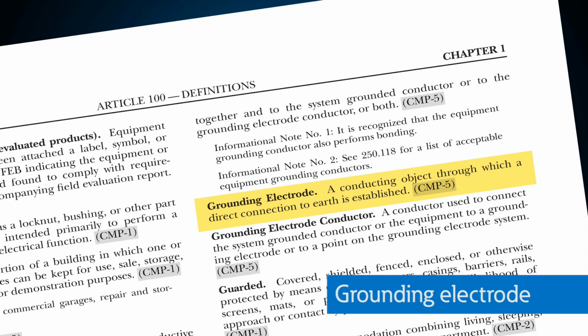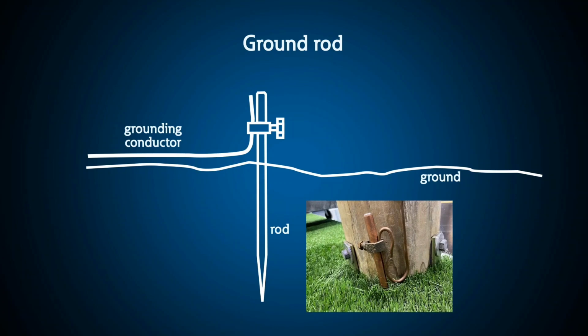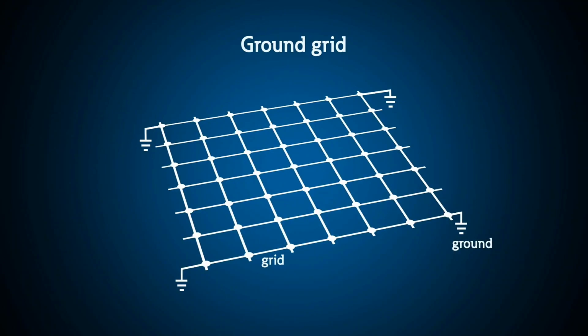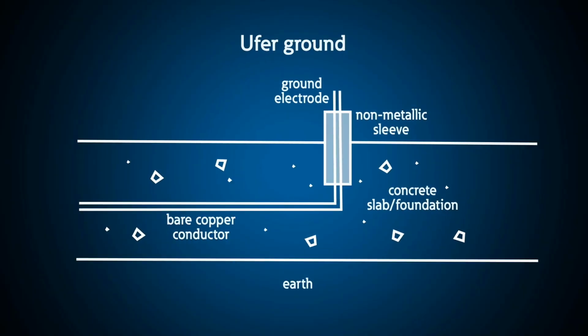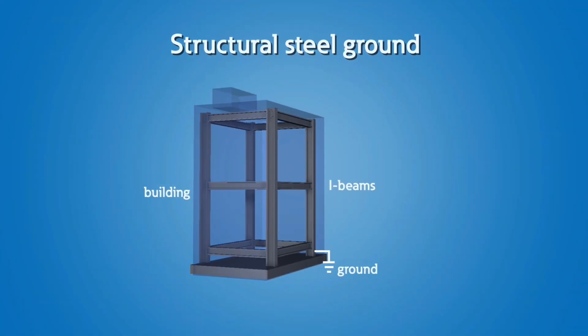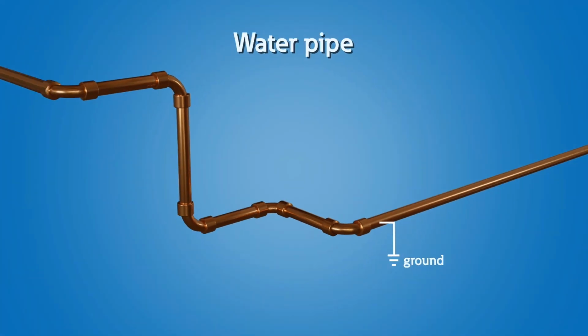Because the earth does not come with terminals, we have to establish a connection to earth, and we do that through what we call the grounding electrode. So a grounding electrode is a conducting object used to make a direct electrical connection to the earth. This is typically your ground rod, a very common solution. It could be your grounding grid, it could be the Ufer ground, or inside of a building it could be the structural steel or the water pipe coming into your home. Those are all grounding electrodes. And you could have multiple grounding electrodes at any one installation.